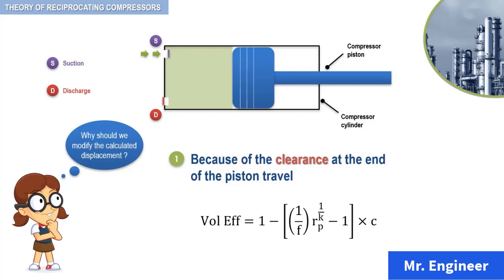The second reason for modification of the displaced volume is that in real-world applications, the cylinder will not achieve the volumetric performance predicted by this equation. Therefore, it is modified to include empirical data. This new equation is the one recommended by the compressed air and gas institute, but it is somewhat arbitrary as there is no universal equation.